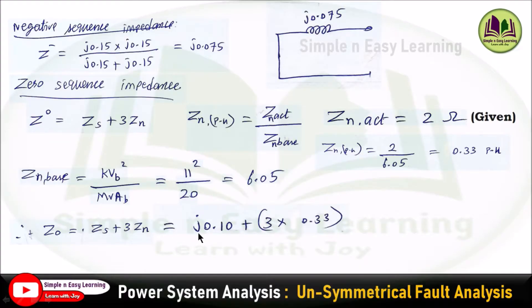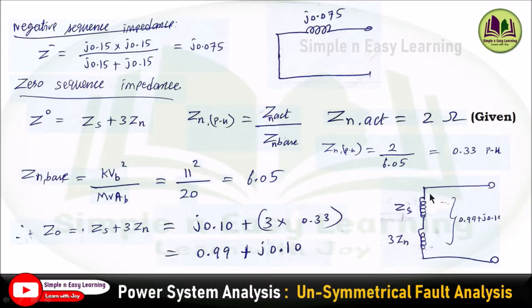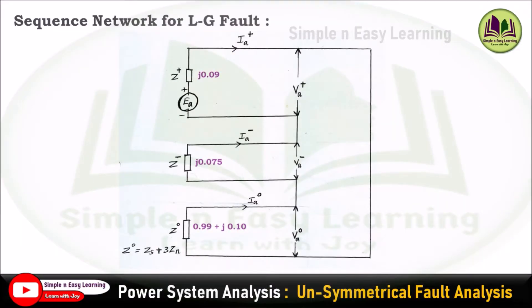Now Z0 = Zs + 3×Zn(pu) = J0.10 + 3×0.33 = 0.99 + J0.10. This is the zero sequence impedance. It can be represented in the sequence network with impedance Zs + 3Zn having value 0.99 + J0.10. The complete sequence network for this single line to ground fault is drawn by substituting all values.